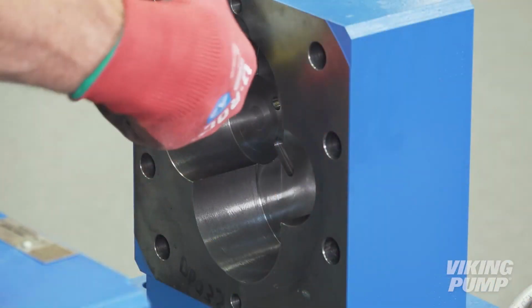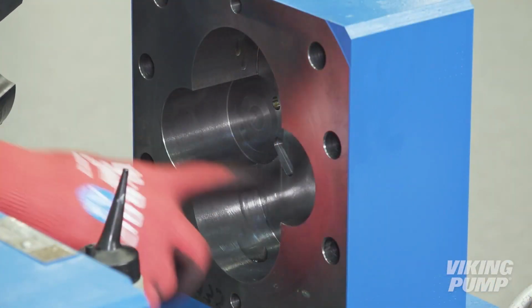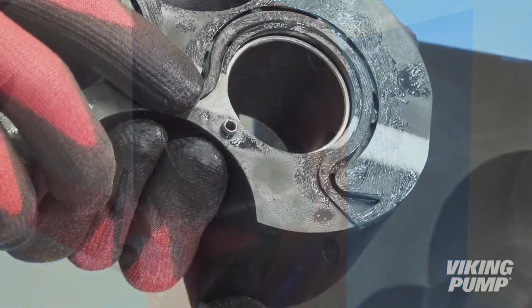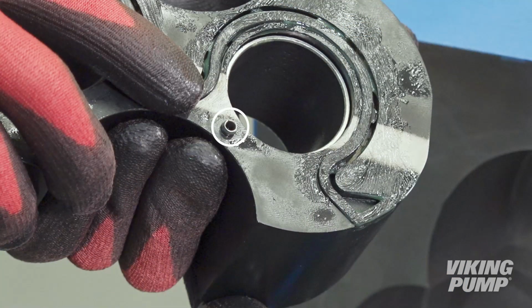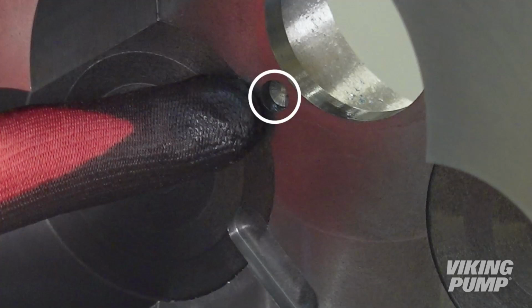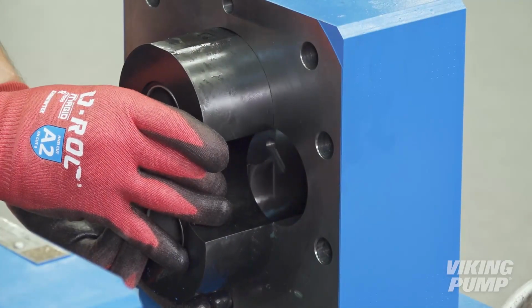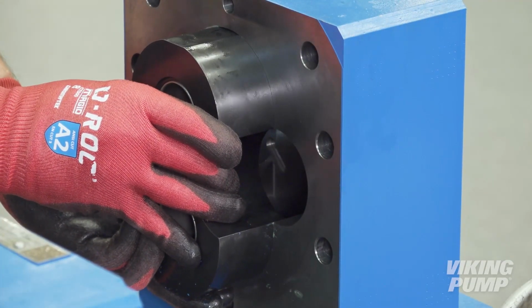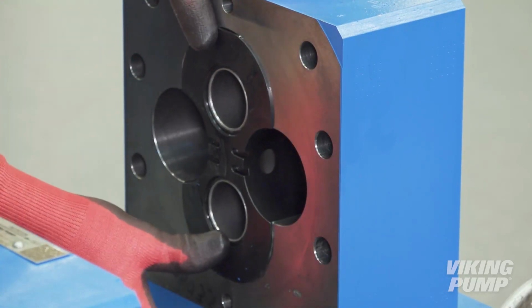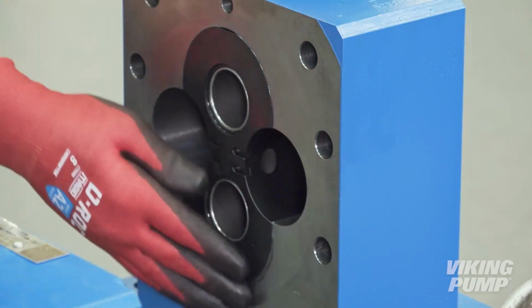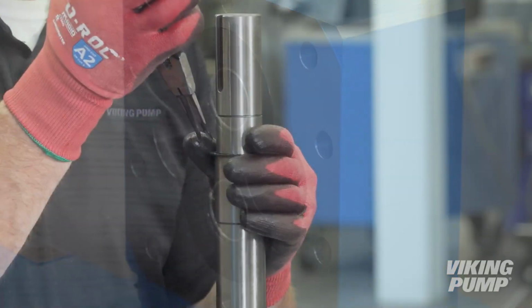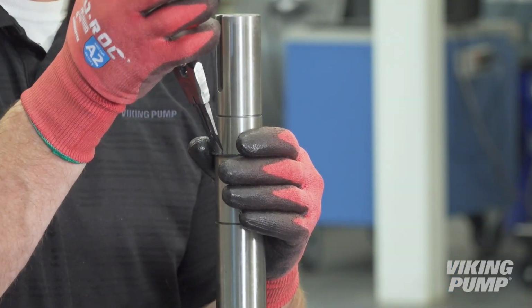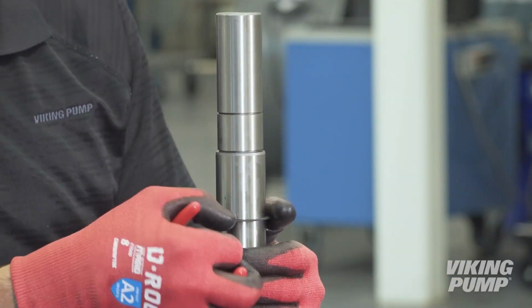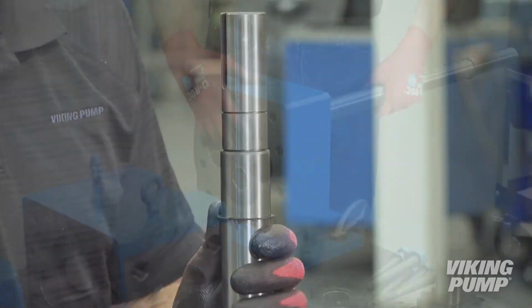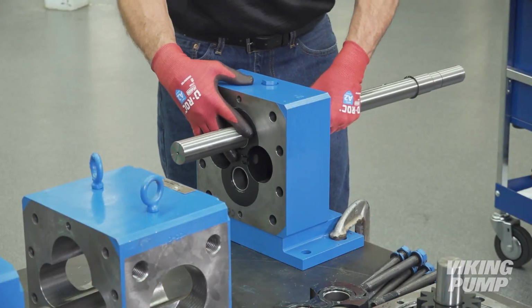Apply light oil to the bushing block and bracket bores. When installing, make sure to line up the bushing block pin with the groove in the bracket. It may be necessary to use a soft-headed hammer to gently tap the bushing block into place. Be careful not to damage the faces of the bushing block. Next, using the snap ring pliers, install the external retaining ring to the shaft. Install the shaft through the motor end of the bracket.